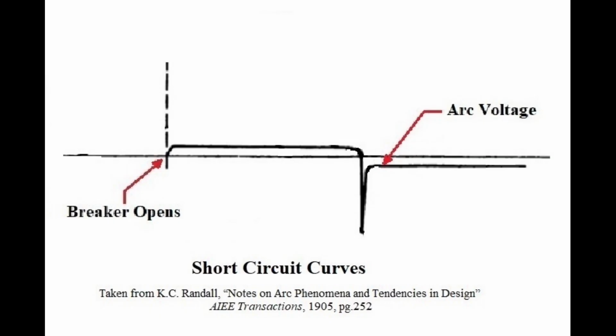Under these conditions, the frequency of the current in the line is complex and often produces a fault distant from the point where the short occurred. To understand this situation to the point where accurate predictions of fault levels could be made would take years. Not until the digital computer came into widespread use in the 1980s could this be accomplished with a high degree of certainty.